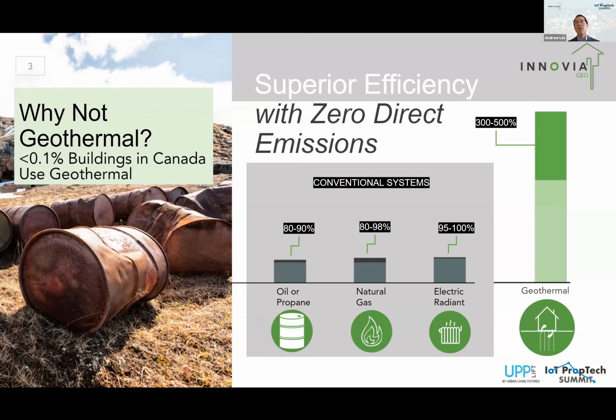Because we're moving heat and not burning a fuel, geothermal is incredibly efficient and has zero direct emissions. For every 1 unit of electricity needed to run a geothermal system, you typically move 3 to 5 units of usable heating or cooling energy into a building.